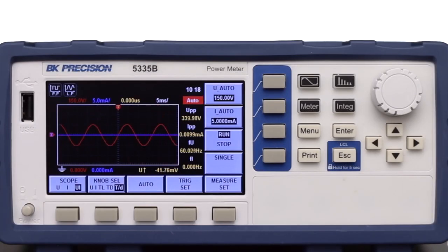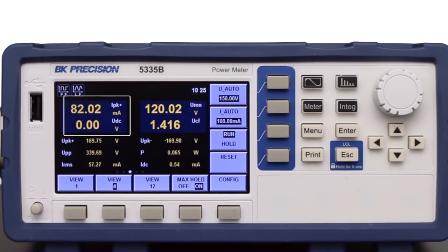Evaluate total harmonic distortion and harmonics up to the 50th order with the ability to display individual harmonic components. The oscilloscope function displays a waveform of sampled voltage and current readings in the time domain. Easily capture inrush current and voltage surge using the peak function.